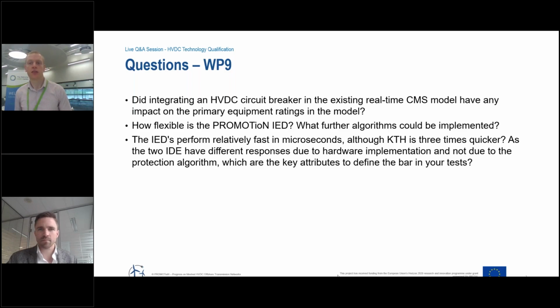I guess it's not just that we tested in the same network in parallel at times. I'm not sure about the latest results, but earlier in the year during one of the other webinars, we even presented some results where the two have been used together. In some scenarios we tested breaker failure on one line, protected by one relay, that would be backed up by the other one, so there was crosstalk between them to cross-operate. That kind of integration, or cross-verification, has been shown pretty well, I think. Interoperability, yeah, exactly.